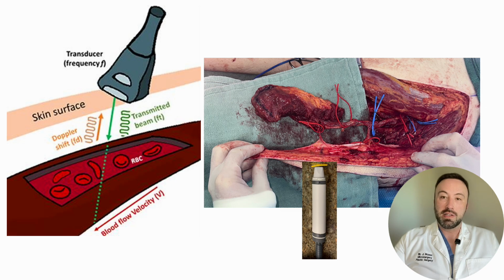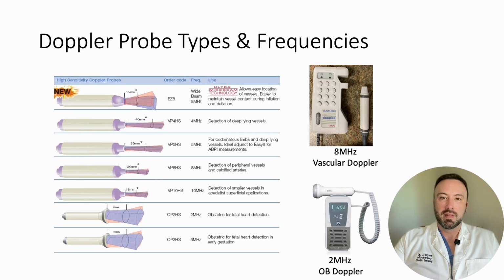So how exactly do Dopplers work? Handheld Dopplers work by emitting sound waves via a probe that travel through tissue, are reflected off moving red blood cells in the target blood vessel, then are detected by the Doppler, giving us audible information about blood flow. There are a variety of different Dopplers available in the hospital with different frequencies that are used for different purposes. It's important to make sure you have the correct Doppler.